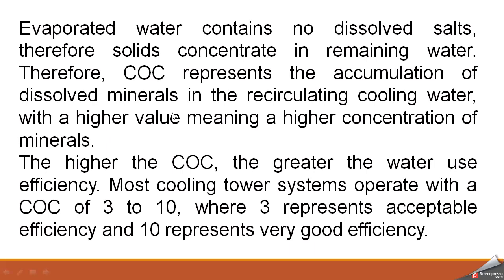If we have a higher value of COC, then this means a higher concentration of minerals, and if we have a low value of COC, then it means a low amount of minerals present in the cooling tower water. So the higher the COC, the greater the water use efficiency. This means that if we have a higher COC, we are utilizing more water and discarding less water.